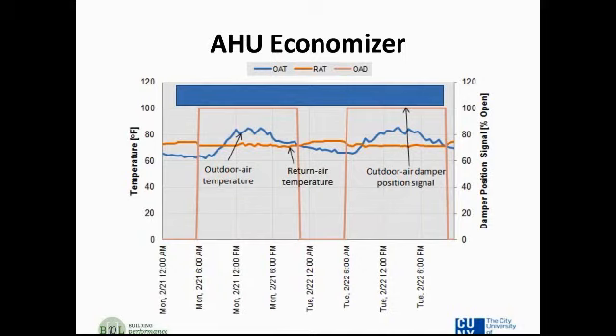The answer is yes, not all day long, but you can see that early in the day the outdoor air temperature is significantly lower than the return air temperature. When that's true, you can just use the outdoor air. You'd be better off dumping the return air to the outdoors and bringing in fresh air from the outdoors. It may still require some cooling, but it won't require as much as the return air. It's cooler. So that's an opportunity to economize. So during those periods, for example in the first day, for the first couple of hours, the outdoor air temperature is below the return air temperature. And you might want to put a margin in there based on relative humidity if it's humid out, but still.